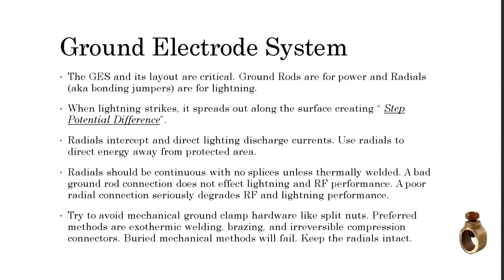Okay, let's talk a little bit about the ground electrode system because it is crucial and it's critical. Now, here's something you need to know and understand. Ground rods are for power and radials are for lightning and RF. Okay? When lightning strikes, it spreads out along the surface, creating what they call a step potential difference. Where that name comes from is the distance between your feet is enough to kill you.